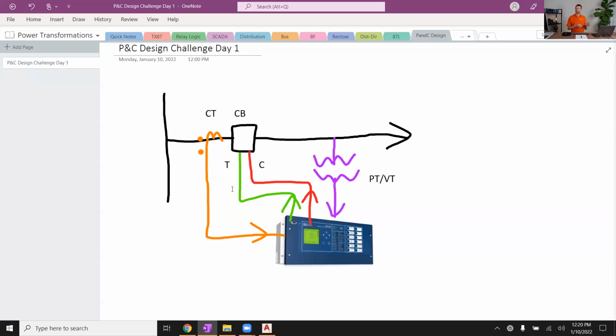This is showing just a single relay. A lot of times we have primary and backup relays as well. But this is about as simple as I can make it from a high level perspective, the essence of what you should expect from a protection system. CTs and PTs coming into your relay, trip and close signals coming out of your relay. There's usually other DC type signals coming in and out of our relay as well. Sometimes we choose to put those on a one line, other times we don't. We'll go into that more tomorrow. But this is the bare bones that you should expect to see on a one line.